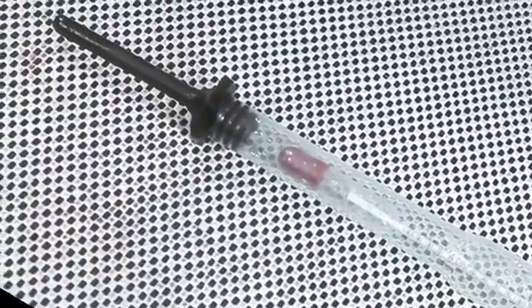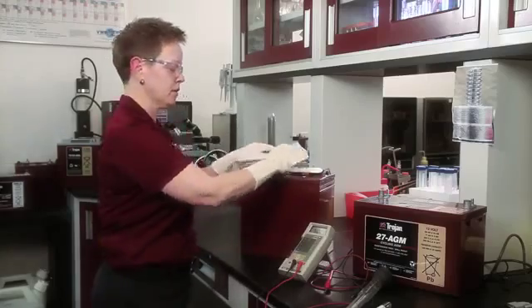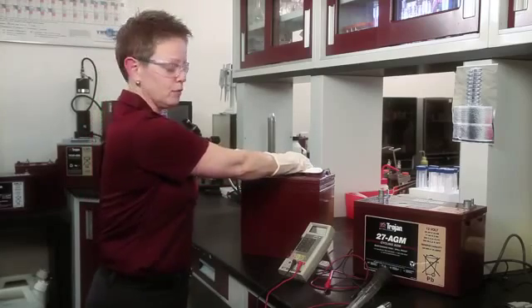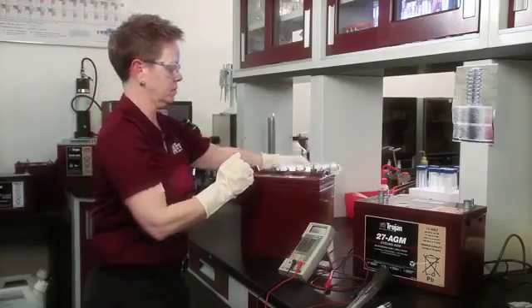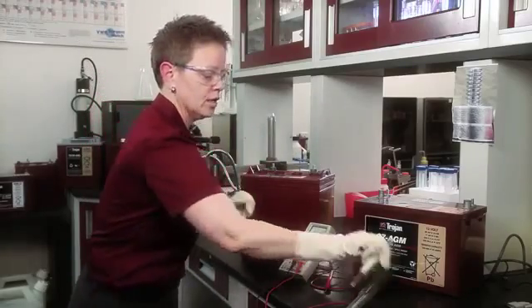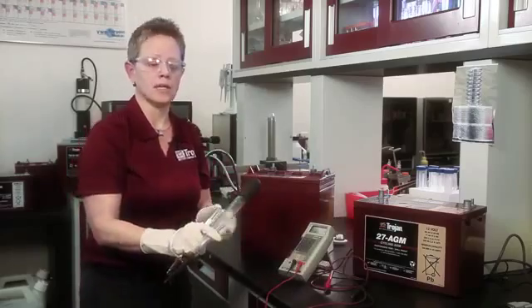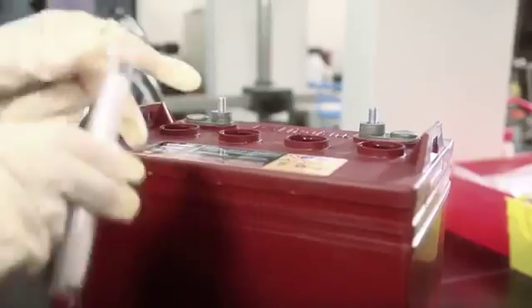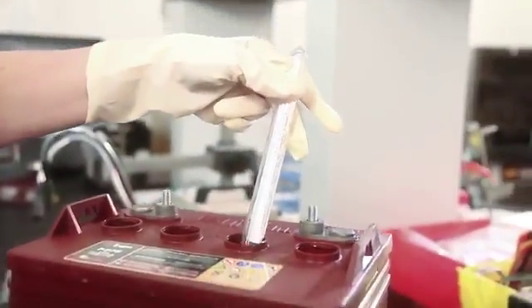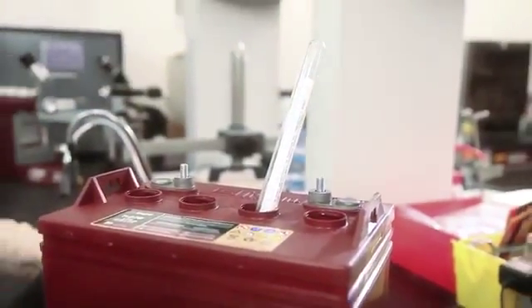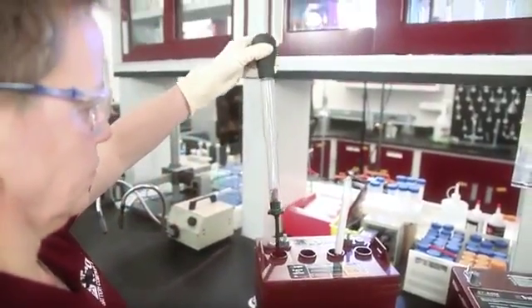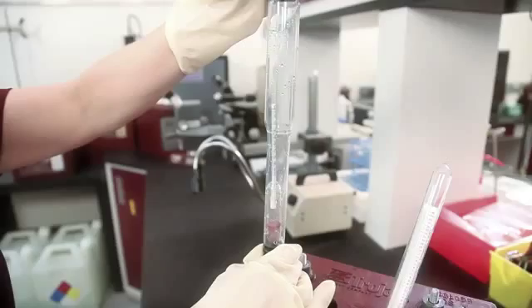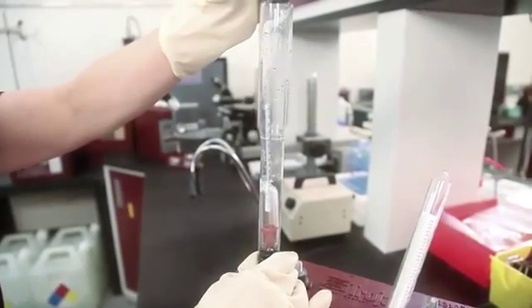This is a very inexpensive hydrometer that you can purchase from a local automotive parts store. What you need to do is gain access to the battery by removing the vent, and always be careful to remove the vent away from your face. It's important when you're reading specific gravity that you temperature correct the value. So you should always have a thermometer. Place the thermometer in a center cell in the battery. Take the hydrometer and insert it into the cell of the battery and siphon out the electrolyte.